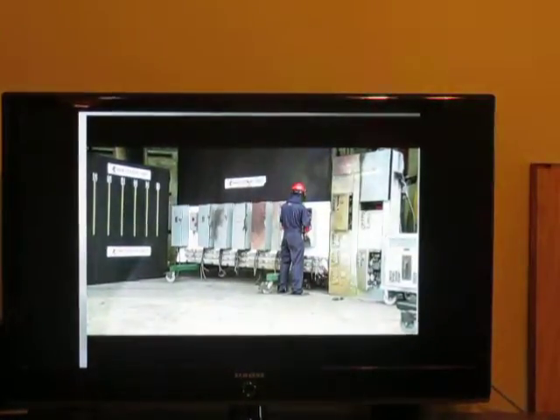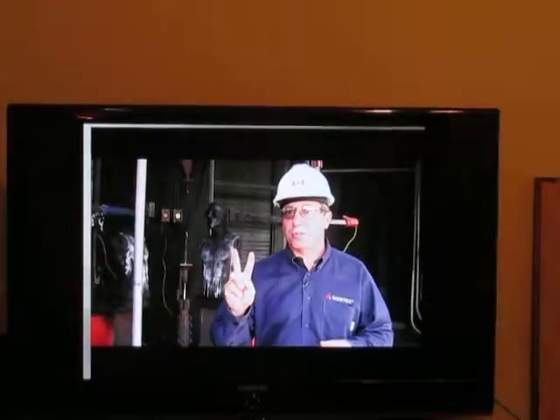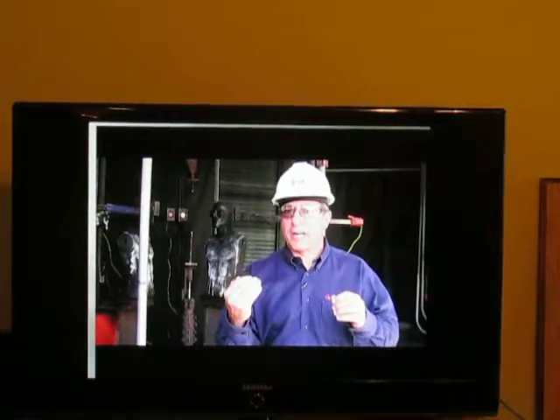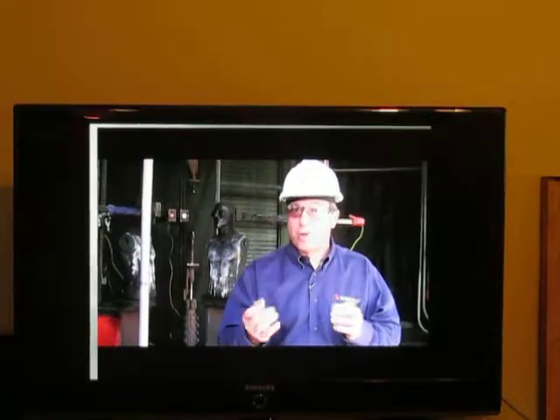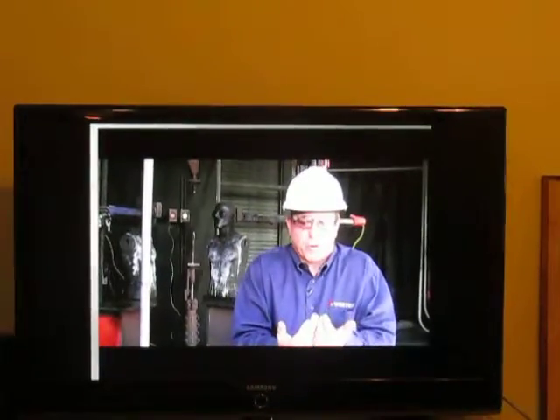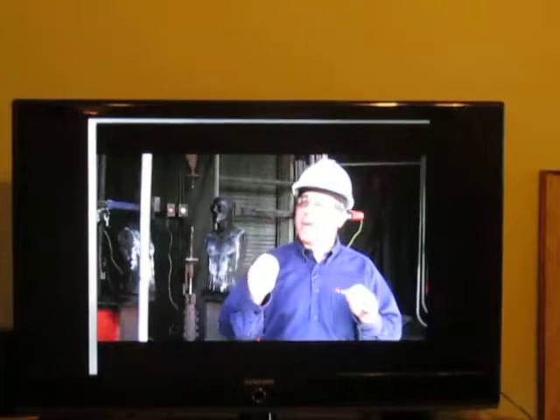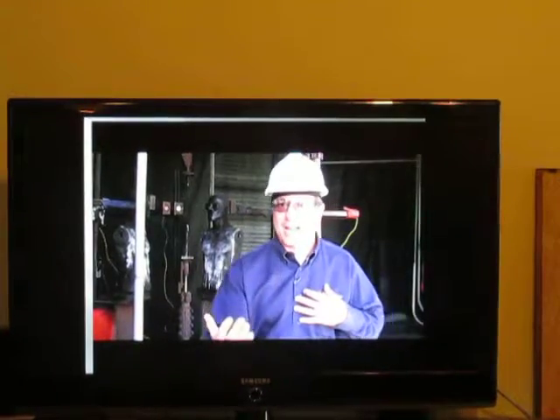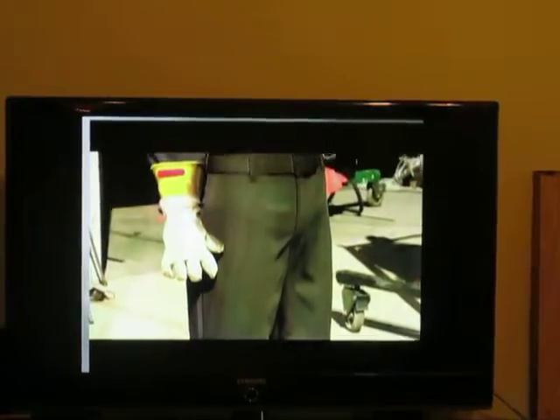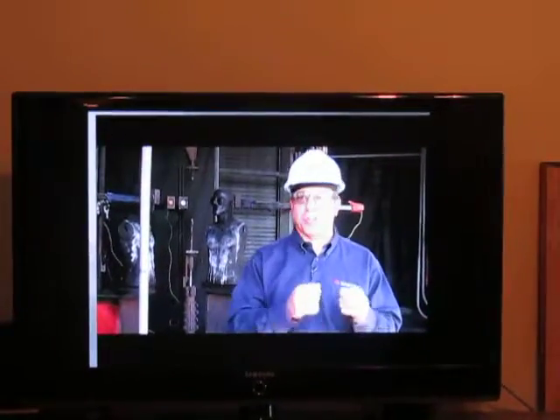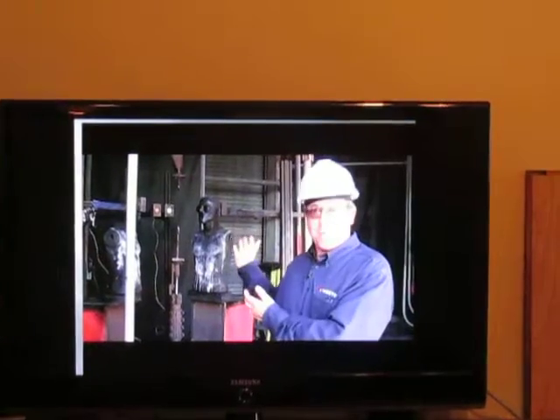Arc-rated clothing achieves 2 things. Number 1 is for the fabric not to ignite and continue to burn when the heat source is removed. The second thing that you want that fabric to do is, once you've gotten to the point where it doesn't ignite, now you'd like it to insulate you as well from whatever hazard you face, so that not only is your burn not made worse by ignition, but also you're not burned at all because it's insulating you against that hazard. Scott warns people not to confuse arc-rated clothing with flame-resistant clothing. All arc-rated clothing is flame-resistant. It has to be flame-resistant just to get in the test apparatus. But not all flame-resistant clothing has been arc-rated by the apparatus.